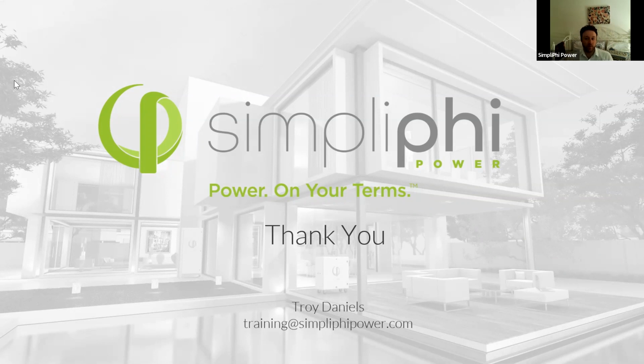If you're not using one of our all-in-one solutions, you have to look at the inverter manufacturer's transfer time. But typically, any battery-based inverter is going to be milliseconds. Now, I will say that not all of them are UPS rated technically. Our Solar unit is actually UPS rated, so if you are pairing with a Solar inverter and our batteries, that actually is UPS rated, uninterrupted power supply.